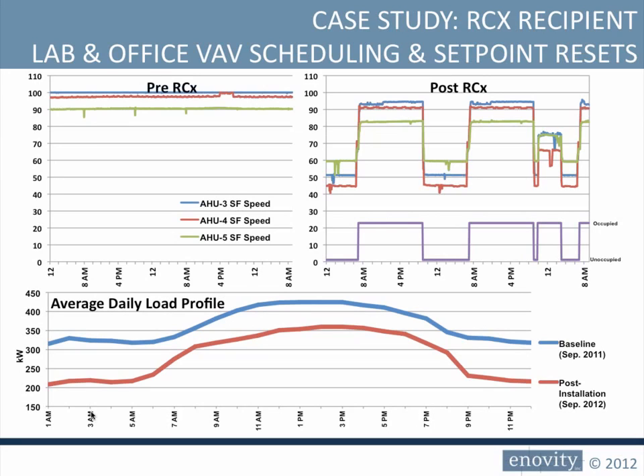By implementing the schedule and closing off the VAV boxes that didn't need to be on all the time, you can see that the fan speeds reduced drastically between the occupied and the unoccupied times in the post period. Before, they were operating at a constant speed. Not all of them were at 100%. One was at 98 or 97, one was at 90, and then you can see in the post case them turning on and off to maintain static pressure in the ductwork, which resulted in, obviously, a lot of energy reduction.